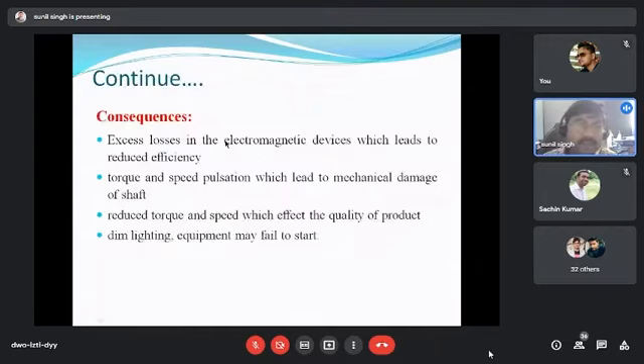What is the consequence of this voltage unbalance problem? Voltage unbalance always exists in the distribution network. The perfect balancing of the voltage is not there. So that's why there is excess loss in electromechanical devices, which leads to reduced efficiency. We are talking about three-phase devices. And torque and speed pulsation is another very important consequence, which requires more research in this area. What is the impact of the voltage unbalance on the speed and torque pulsations or mechanical damage of the shaft?